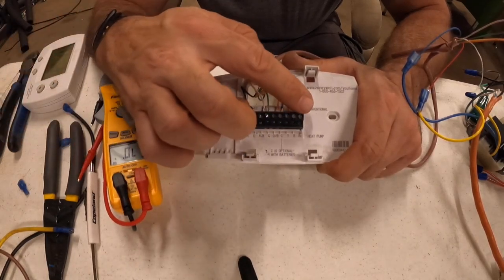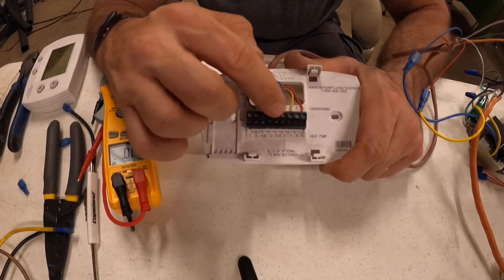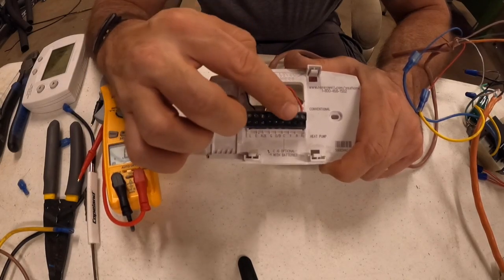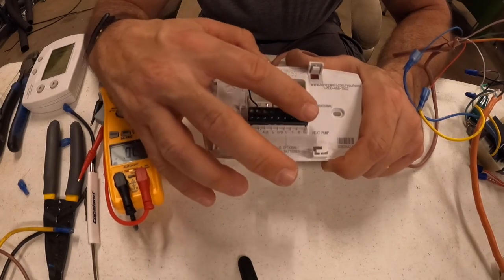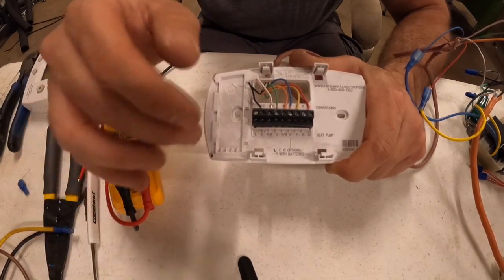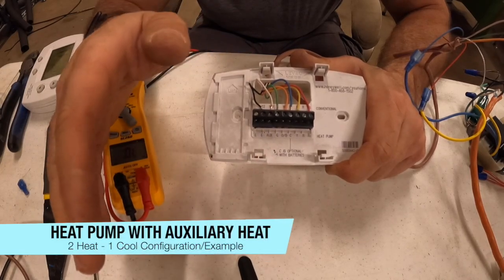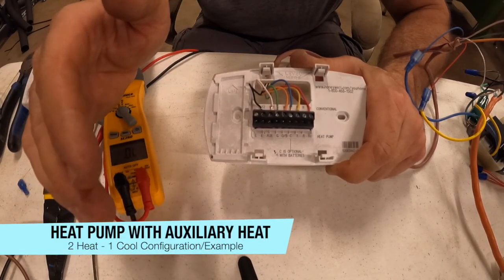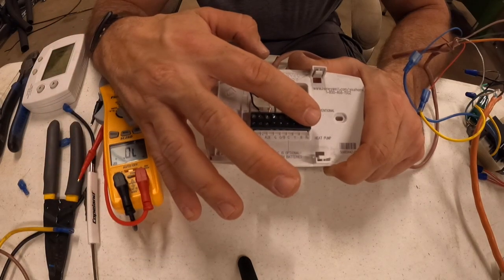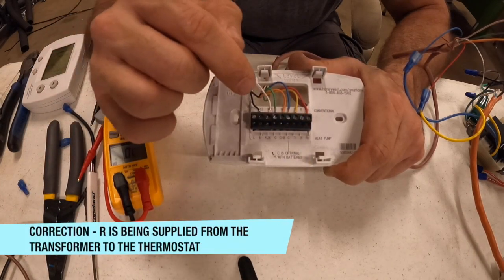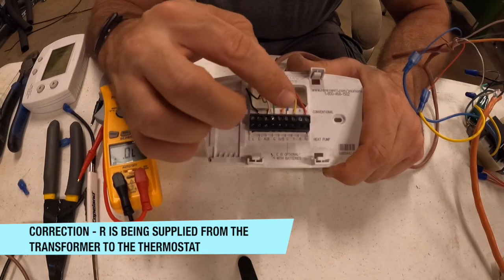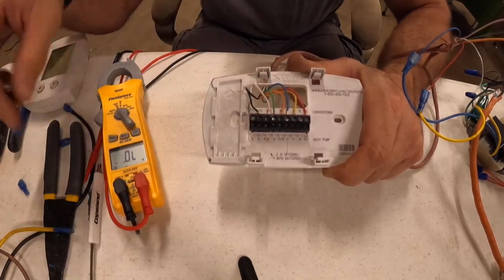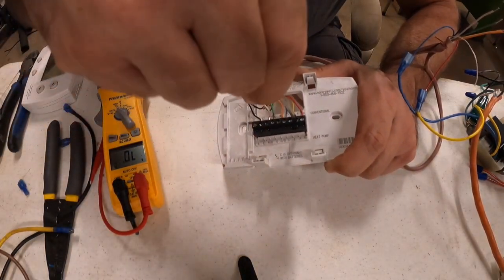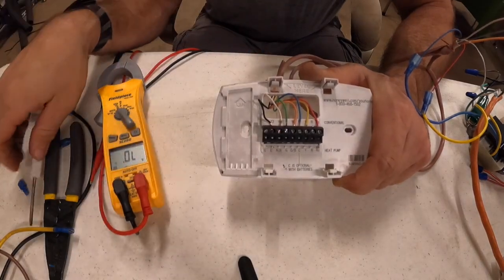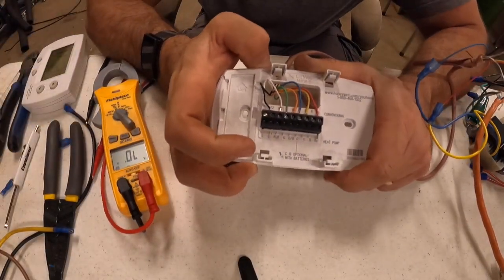as to where it directs the power from this R or RC into these other terminals. But for this video, this is going to be basically a 2 heat, 1 cool heat pump system, or heat pump with auxiliary heat. So R is coming from the transformer, that's the 24 volts. R and RC are jumped out. We won't get into what that's all about, but it's for systems that have 2 transformers, so you can separate the 24 volts coming in for each transformer.